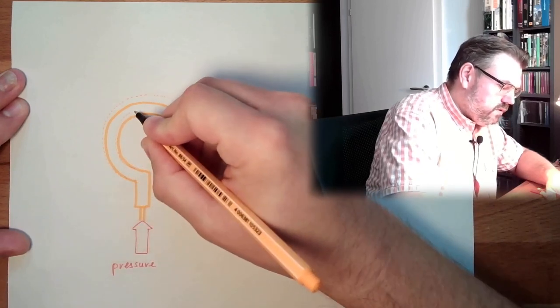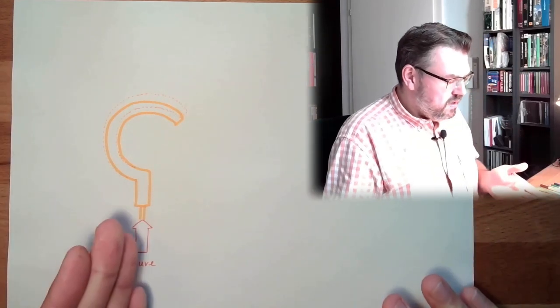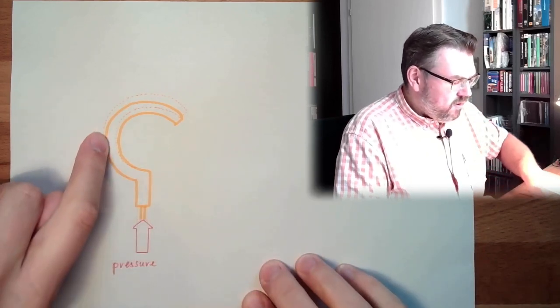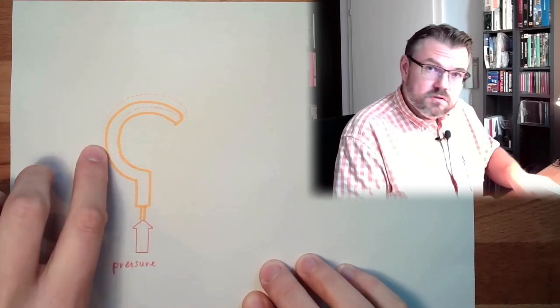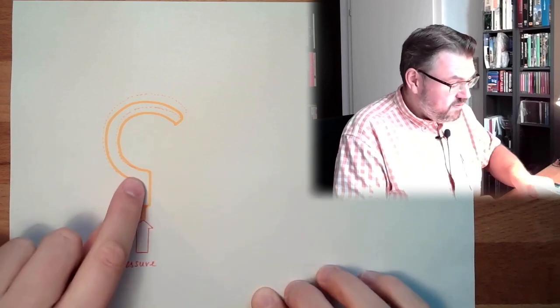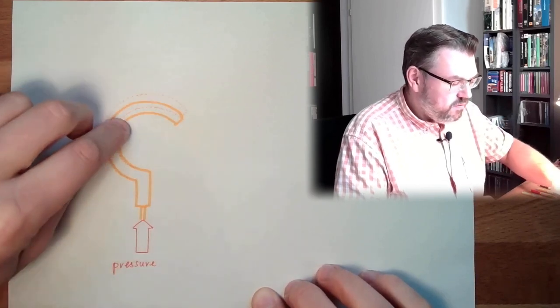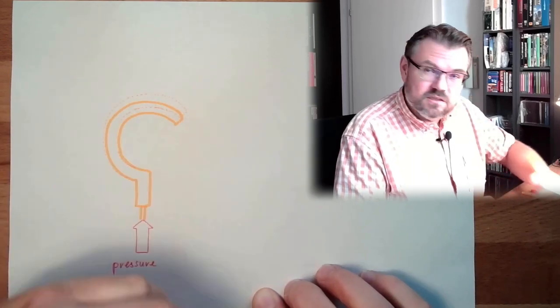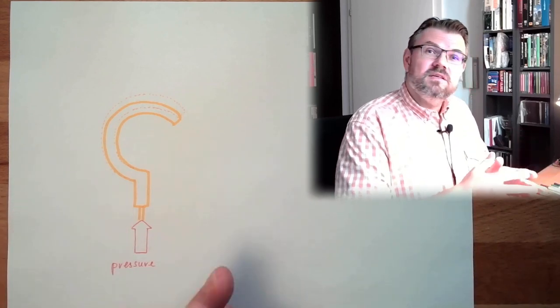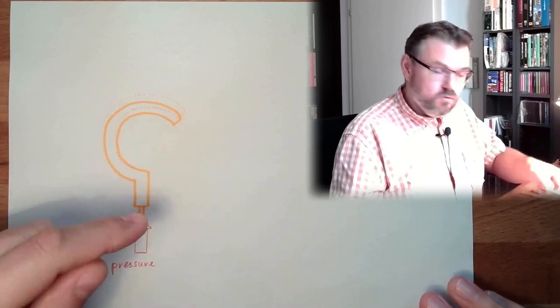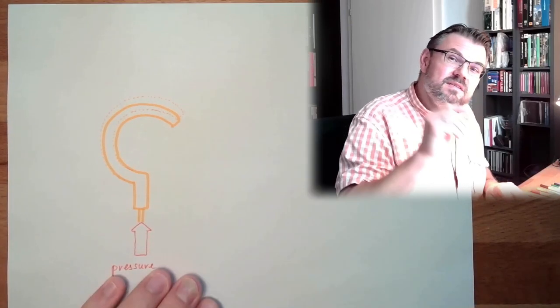This illustrates the principle. If we apply pressure, the tube will try to straighten out and will move. Why does it straighten out? Because the outside area is bigger than the inside area. The applied force from pressure — pressure is force per square meter — and if I have more square meters on the outside, the applied force on the outside is bigger than on the inside. So the force will stretch this until the mechanical stress is big enough to hold it in shape. This must stay inside the elastic area of the material used for this tube, so those changes are small and tiny.